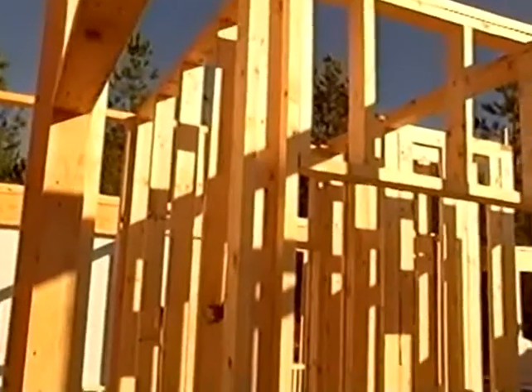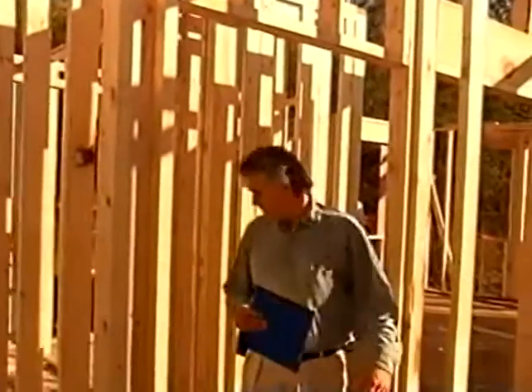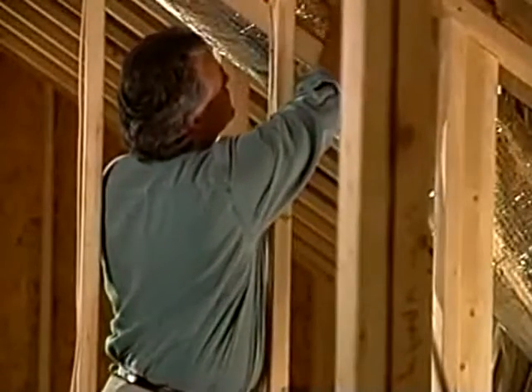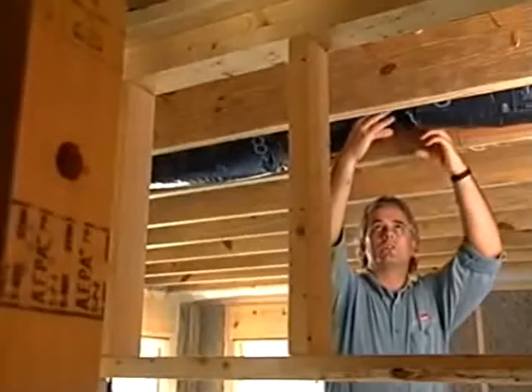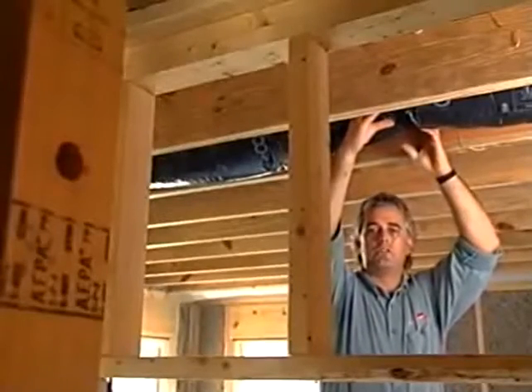So we find ductwork looks sometimes like pressure is being squeezed to get through spaces. We have 6 squeezed through a 2x4 area. So we see all these constrictions, and these all create problems. Dan McFarland is a building science expert with Advanced Energy Corporation. He sees countless examples of air distribution systems choked off because of improper installation. In this situation, the contractor put his hangers up too high into the joist space. This is creating a constriction in this flex duct, and all along there's a hanger. If he had put the hangers a little bit lower, we wouldn't have had this problem.